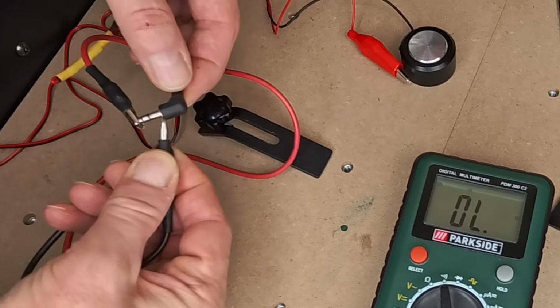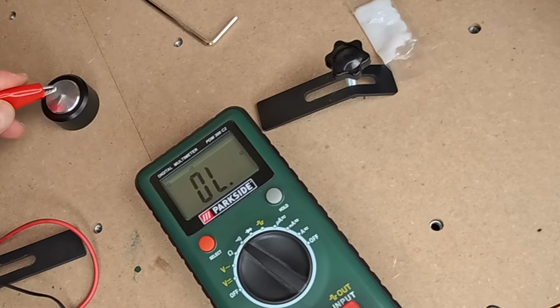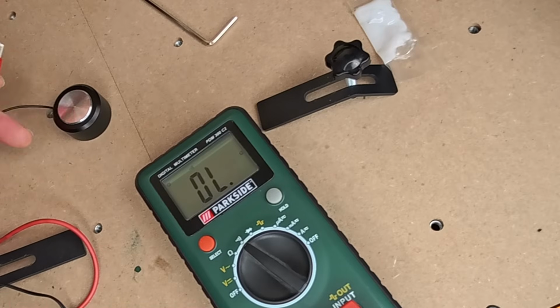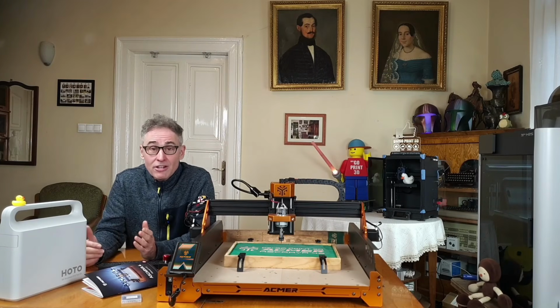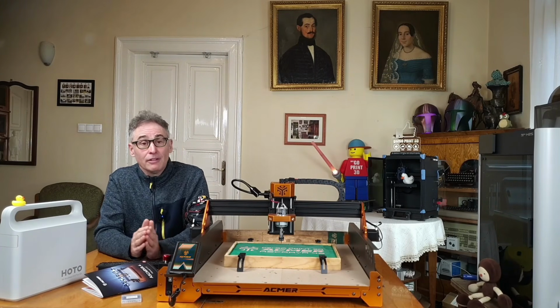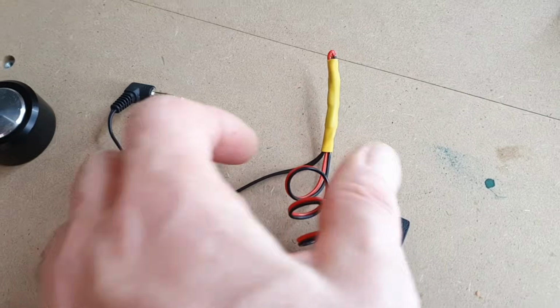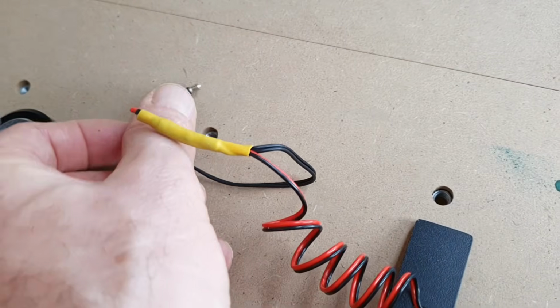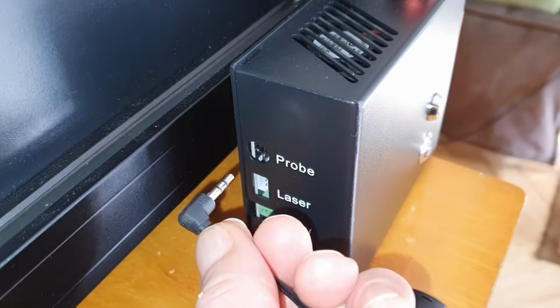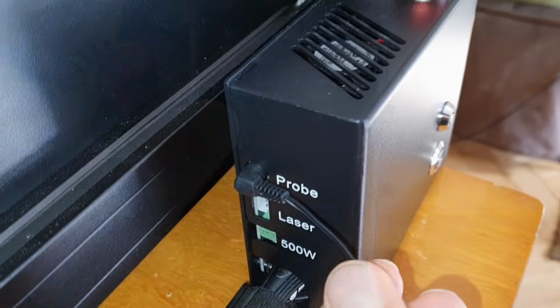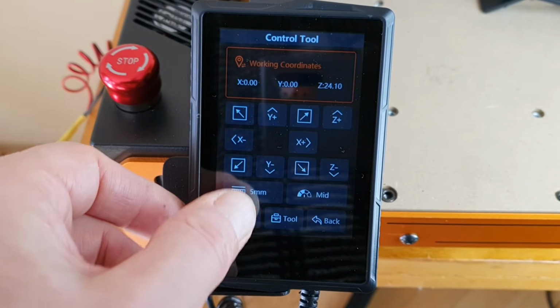Using my multimeter, I confirmed that touching the alligator clip to the probe block didn't close the electrical circuit. Eventually, I narrowed it down to a connection failure in the standard 3.5mm jack, which was easy enough to fix by soldering on a replacement from an old pair of headphones. With the repaired probe, the calibration finally completed successfully.